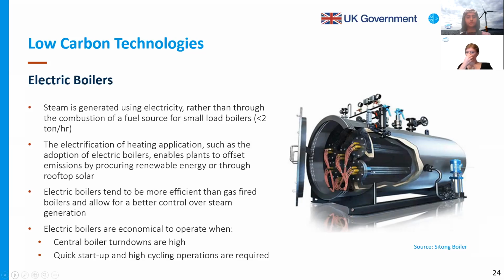So when are electric boilers economical? When the central boiler turndowns are high, the low load operations can be met with an electric boiler, or when your plant is in shutdown, or when you have other typical low load operations. Instead of operating boilers at high turndown, you can consider using electric boilers to deal with the steam required. When you have applications that require quick startup and high cycling, electric boilers are also ideal economical considerations. Next slide.